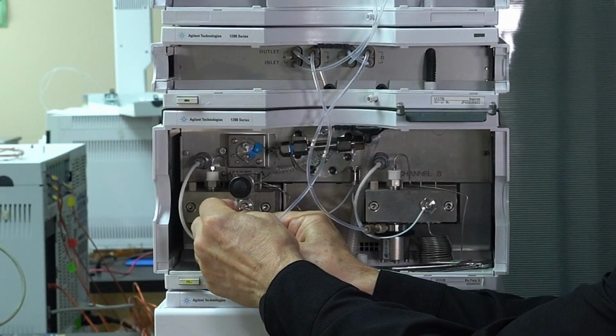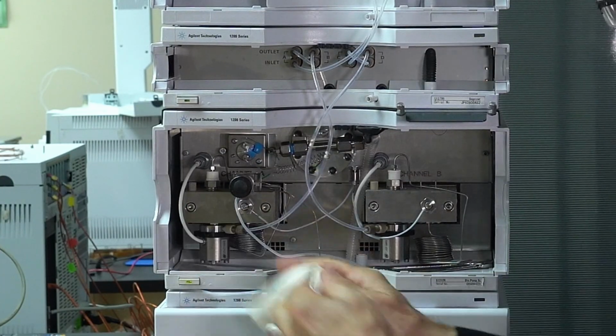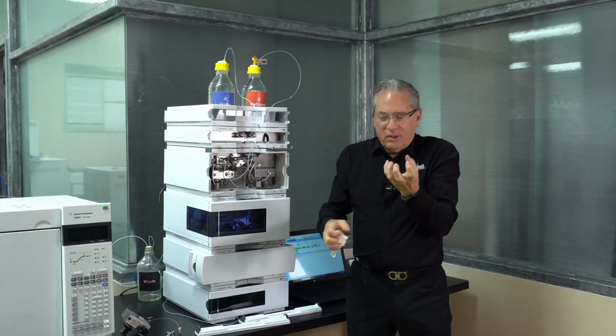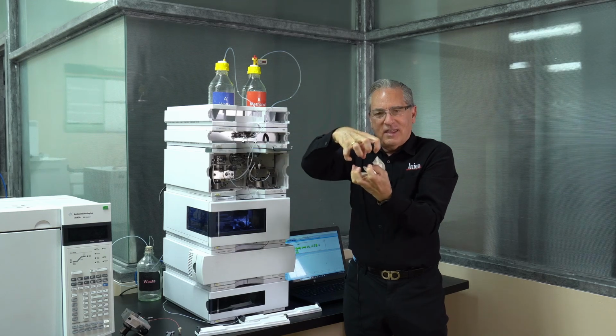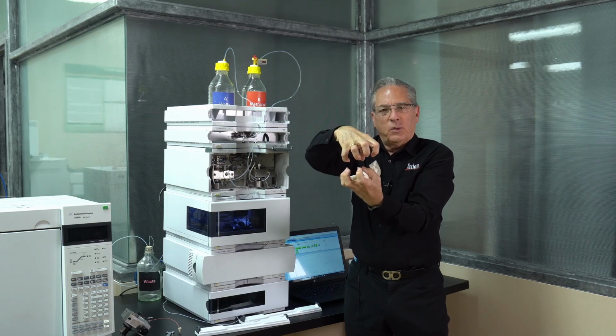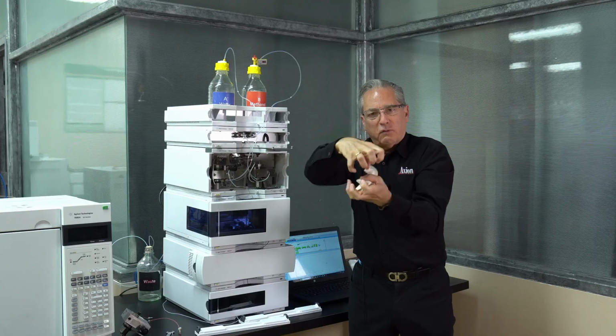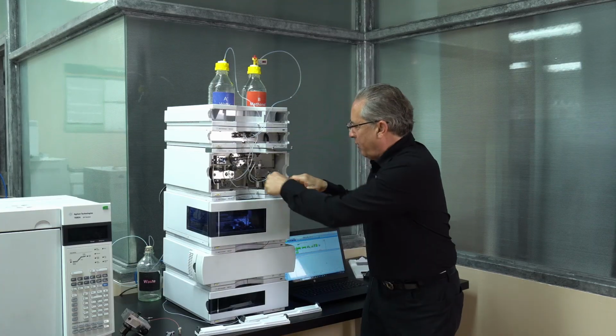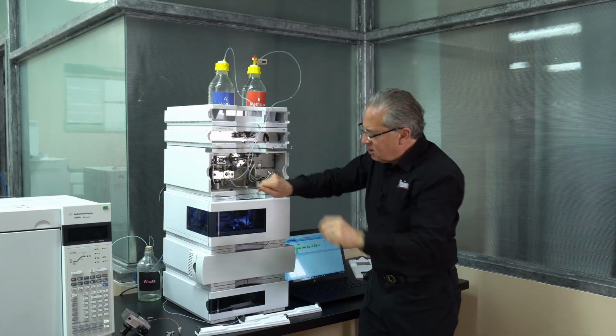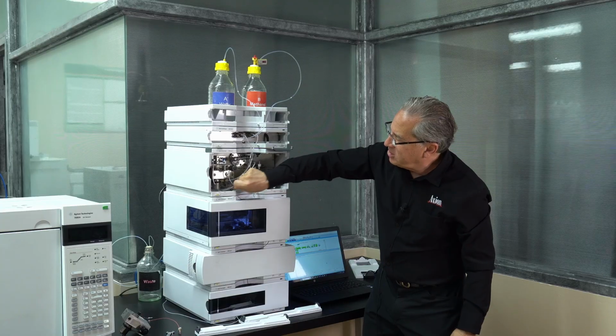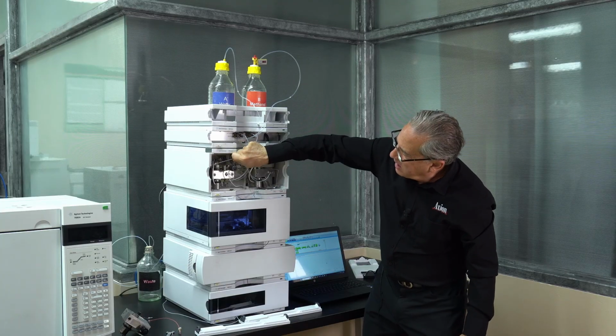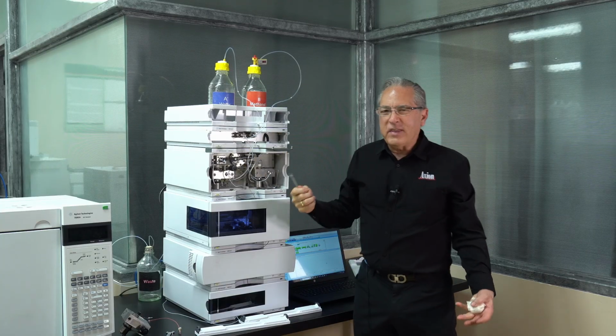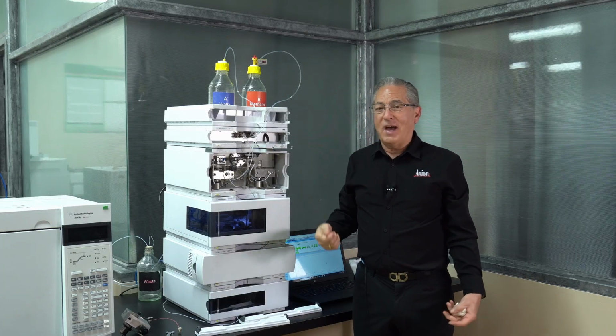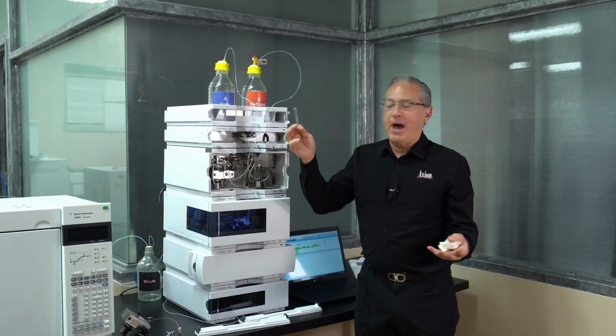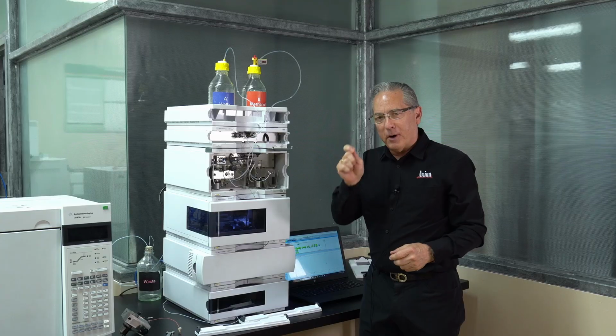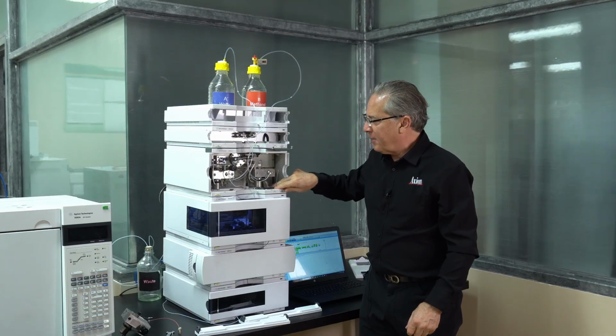Yes. So we're running 5 mils a minute, and the idea is if there's a bubble in there, it's caught underneath the ball and seat, and it doesn't really want to be there. So high flow rate will just sort of flush it out of the way. Some people will take a small wrench and tap on the check valve, inlet check valve, outlet check valve. I don't think the tapping really hurts or helps. I think it just makes you feel like you're doing something. So if you want to tap, go ahead and do it. Don't pick up a hammer, right? Just something small to tap on.